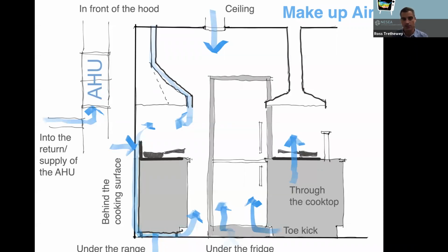The devil's in the details. One example is if you start to bring the air in behind the cooking surface, the challenge there is if it's coming in at too high of a velocity, you get a phenomenon called spillage. Basically, you're not going to be capturing the contaminants through your hood, because there's air blowing on the cooking surface, which is going to make it migrate into the room, and you're not going to capture it.